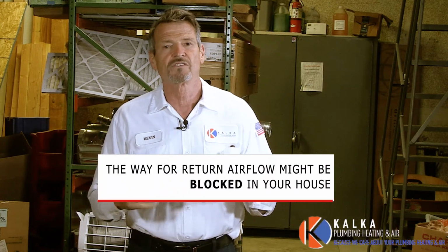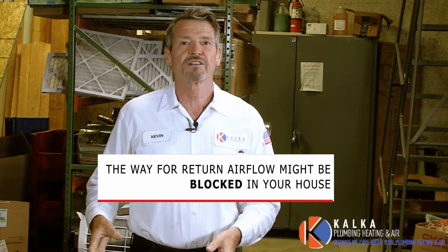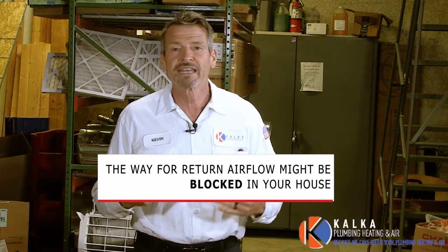One of the other causes too is it could be simple, like you have your return air grill where the air comes into the system. People put boxes in front of it or a piece of furniture in front of it and it can't breathe. If your system can't breathe, it's gonna ice over. One of the other causes though could be, you could be low on refrigerant. If that's the case, then you wanna look up here and check out that video there. But oftentimes it's gonna be airflow.